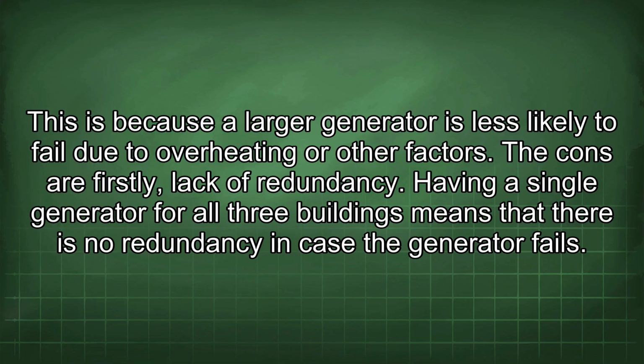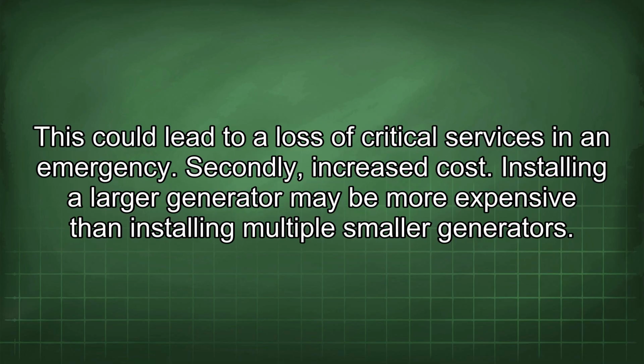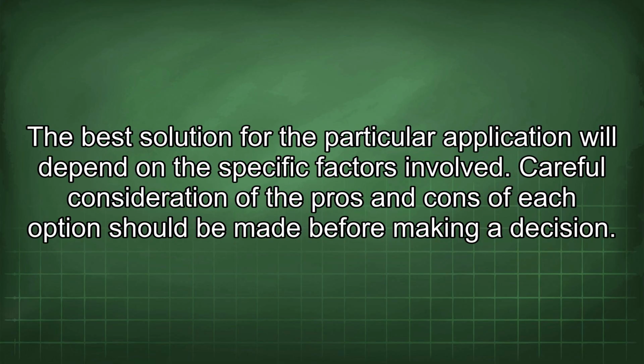The cons are, firstly, lack of redundancy. Having a single generator for all 3 buildings means that there is no redundancy in case the generator fails. This could lead to a loss of critical services in an emergency. Secondly, increased cost. Installing a larger generator may be more expensive than installing multiple smaller generators. The best solution for the particular application will depend on the specific factors involved. Careful consideration of the pros and cons of each option should be made before making a decision.